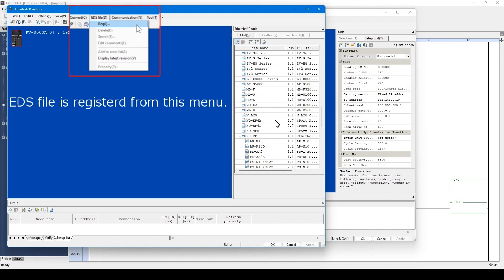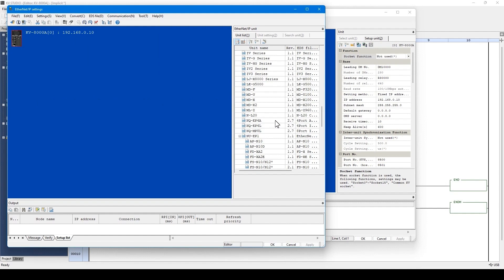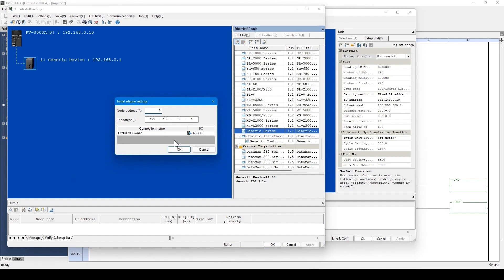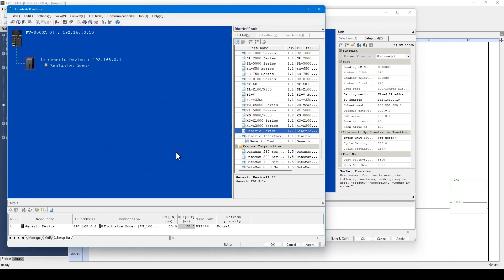In a situation where there is no available EDS file, using a generic device is an option. If the EDS file is not available, drag and drop this generic device. Then enter the IP address set to the robot. In this case, the IP address for this device has been set in advance, so I will click OK without changing any settings.